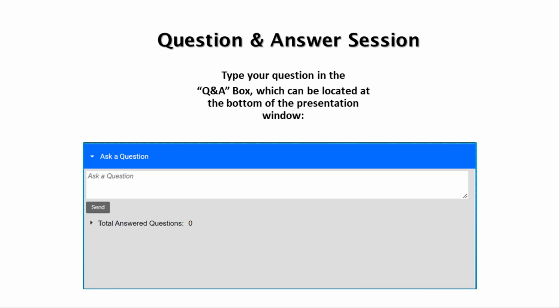Oh, that's a great question. So you don't have to fully revalidate. What you would have to do is a verification. And verifications are described in Chapter 1226 of the USP. In there, it basically says you can do some of the things that would be done for validation, but you don't have to go through a full revalidation.